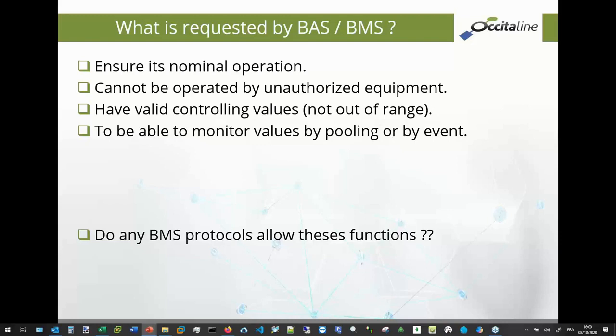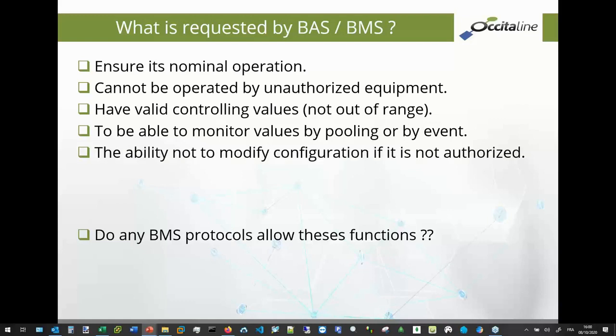Another point is receiving and sending only valid control values. In fact, if you have a range of values for a set point, for example between 10 and 35 degrees, this value needs to be controlled and managed by the device or by the SCADA or by anything else. In fact, you need to have a value in range and not out of range. It's very important.